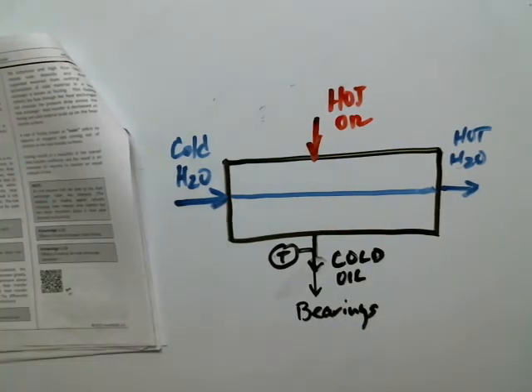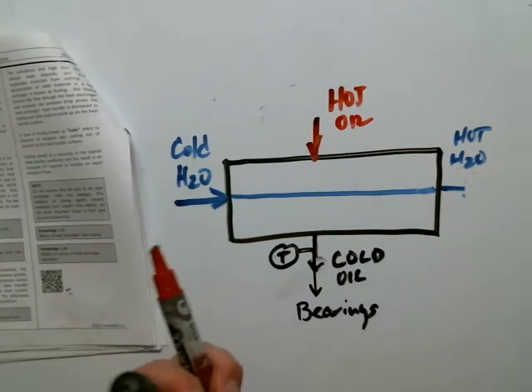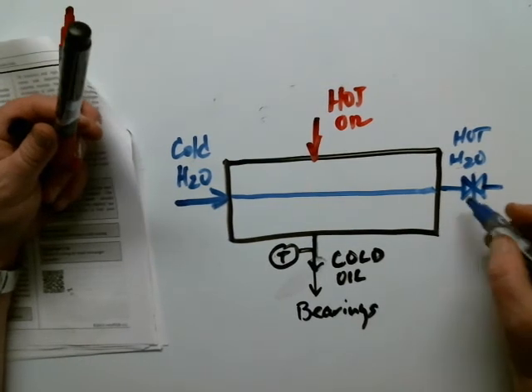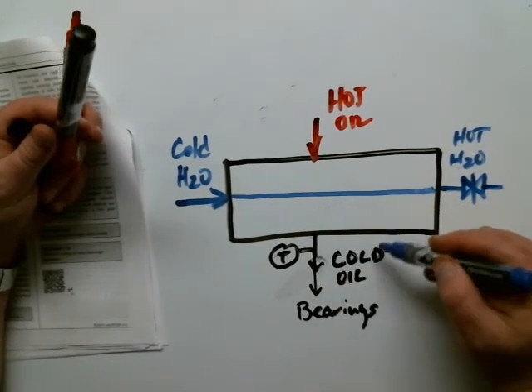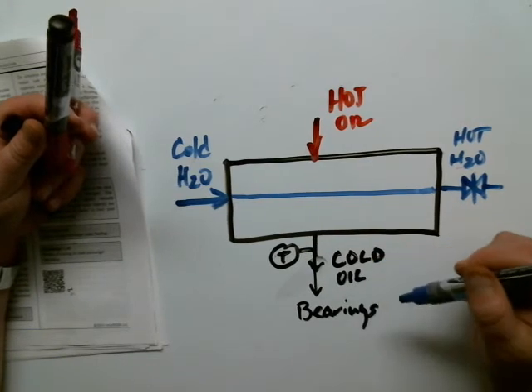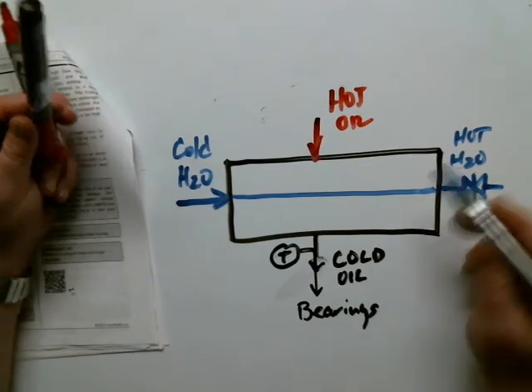So what I'll do is I'll usually have a valve on the outlet of the heat exchanger that I can throttle to control how much cooling water flow I have through the heat exchanger. And that will adjust how much cooling occurs on this oil.